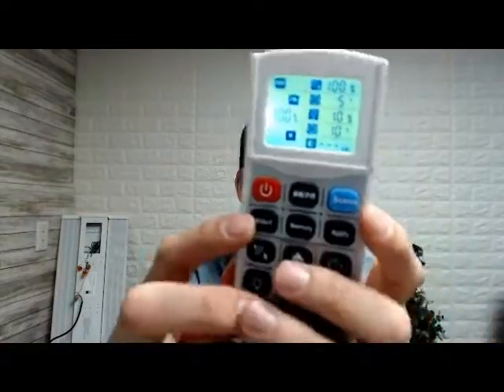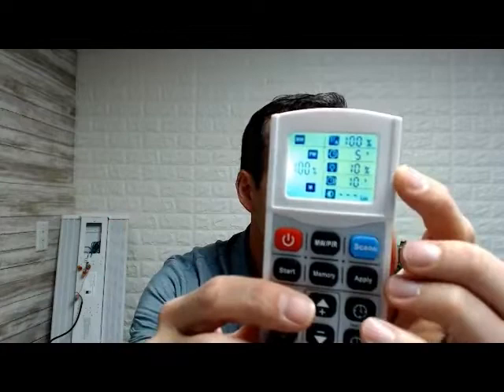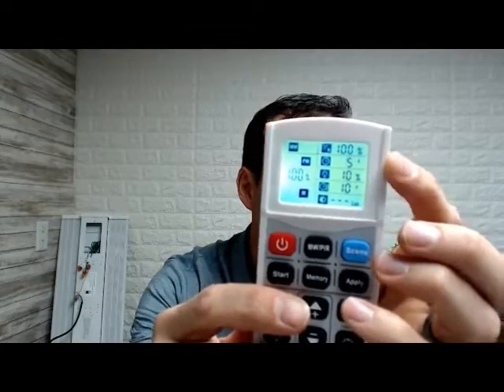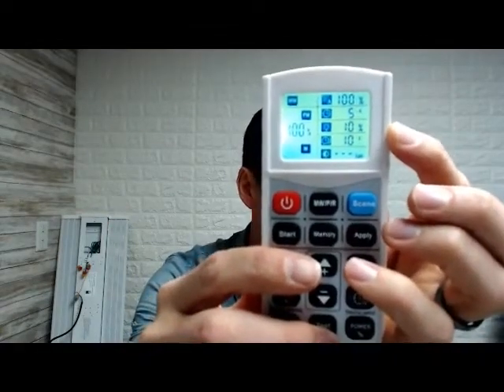I think I'm counting a little bit fast, but now I should turn off on the light. So you can see 100% detection, 5 seconds on, 10% on the dimming level, and then I stay on for 10 seconds after I go down to that dimming level. That is the basic functionality.